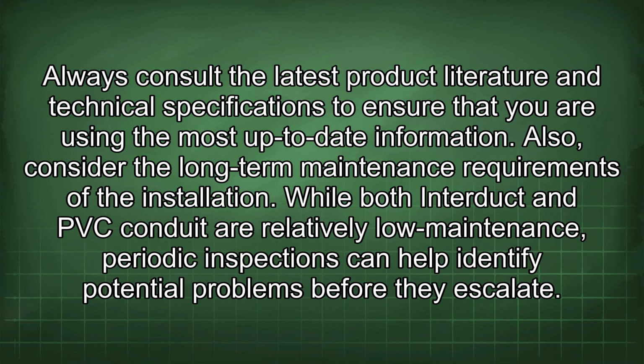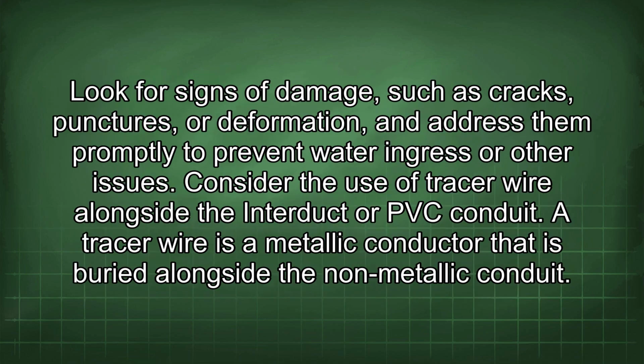Also, consider the long-term maintenance requirements of the installation. While both Interduct and PVC Conduit are relatively low maintenance, periodic inspections can help identify potential problems before they escalate. Look for signs of damage, such as cracks, punctures, or deformation, and address them promptly to prevent water ingress or other issues. Consider the use of tracer wire alongside the Interduct or PVC conduit.